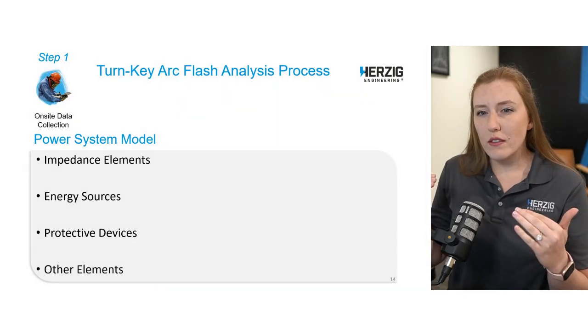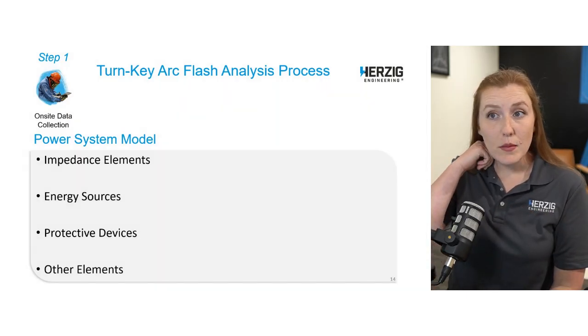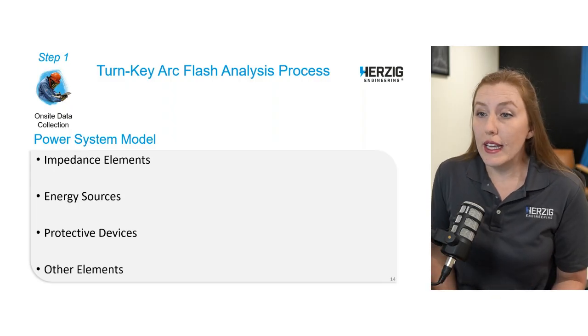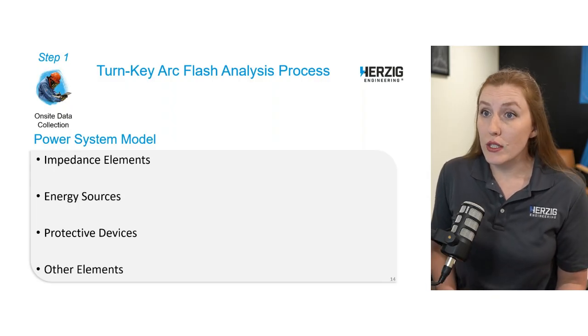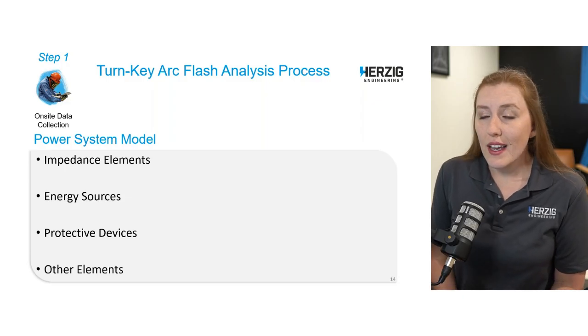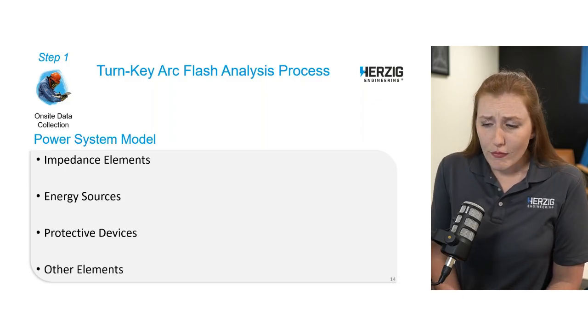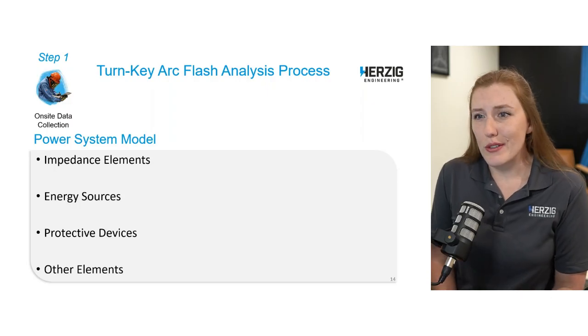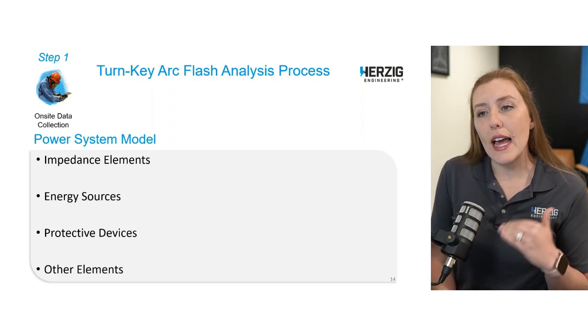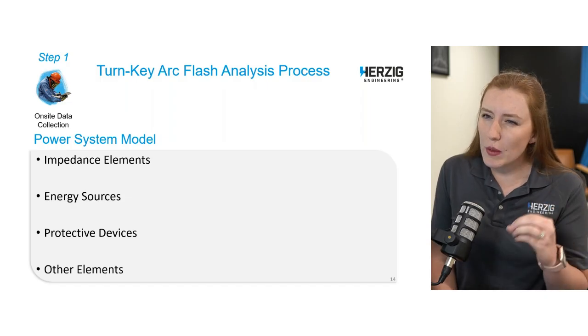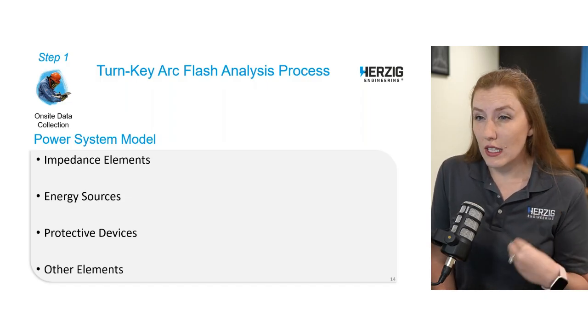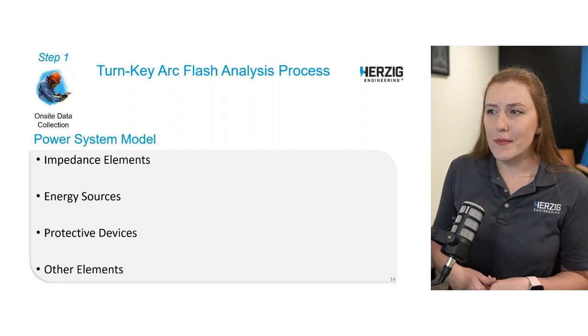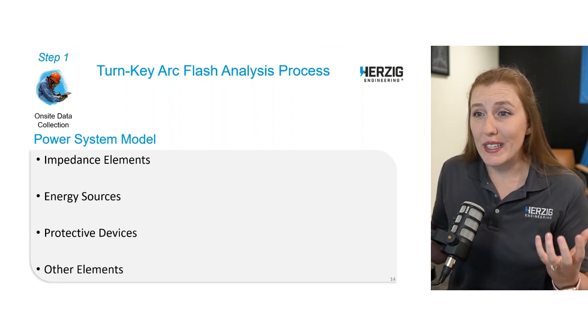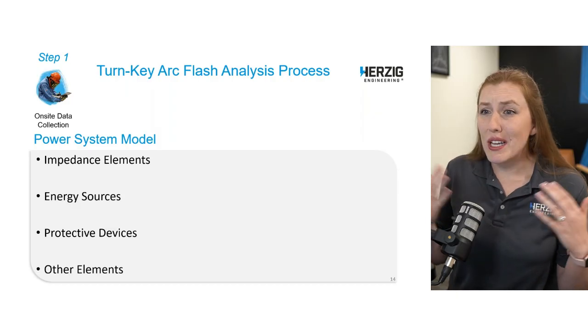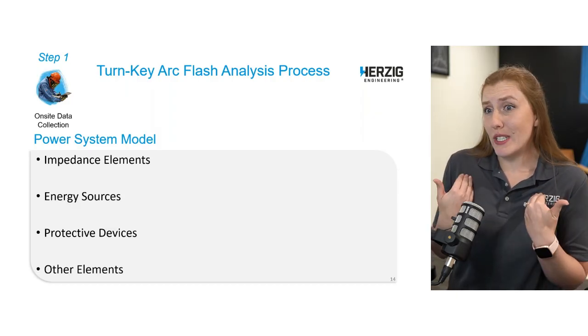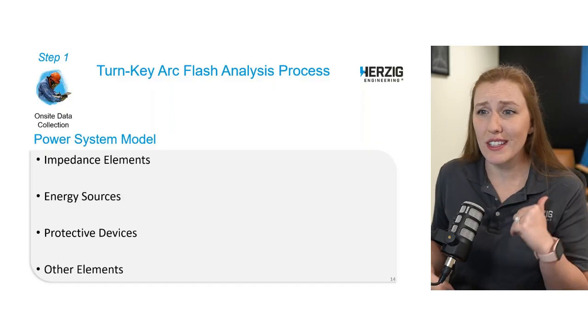So overall, the items that they're looking at are impedance elements, so wires, for example, the energy sources, generators versus utility, protective devices, breakers, relays, fuses, other elements like VFDs and motors and transformers and all the things that are going to be included in that engineering analysis. I'll have a little more detail on what all is collected when we get to the other side, because I want you to know what your people would be expected to collect. But right now, we're talking about the stuff you don't have to worry about because we're dealing with it. It's our turnkey solution. I'm just saying there's a lot that goes into it.